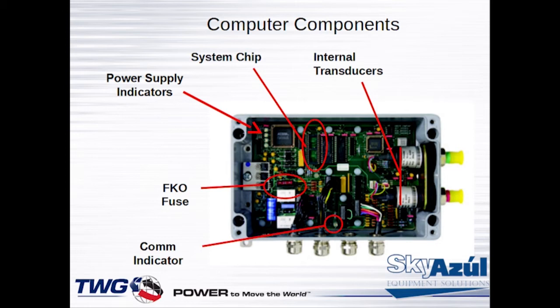The internal transducers are programmed to the board and cannot be changed in the field. There's a COM indicator right here at the bottom part of the board—a flashing indicator. I've had countless calls with somebody saying, well, I found the problem, the light's flashing. Well, it's supposed to—it flashes for two-way communication. That's what it's doing.